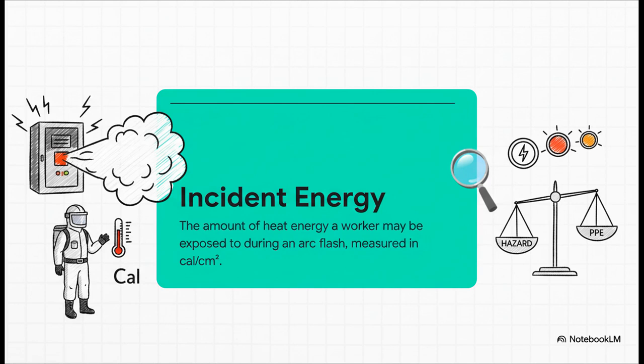But how do you know what PPE to wear? You can't just guess, you have to measure the hazard first. We do that by calculating something called incident energy. The easiest way to think about it is like a dose of heat - how much thermal energy would you get hit with if you were standing at a certain distance. It's measured in calories per square centimeter, and that one number determines everything that comes next.